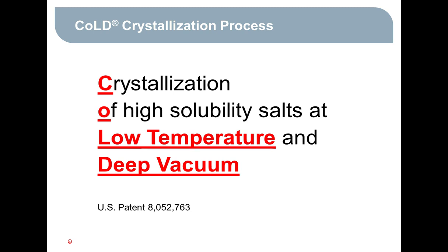It means crystallization of high solubility salts at low temperature and deep vacuum. So this kind of tells you where cold crystallization applies. It applies when you have highly soluble salts like calcium chloride and magnesium chloride, which happen to be the predominant salts in FGD wastewater, and it operates at low temperature, and the low temperature is generated by operating the system in a deep vacuum. Okay? So that's what cold means.